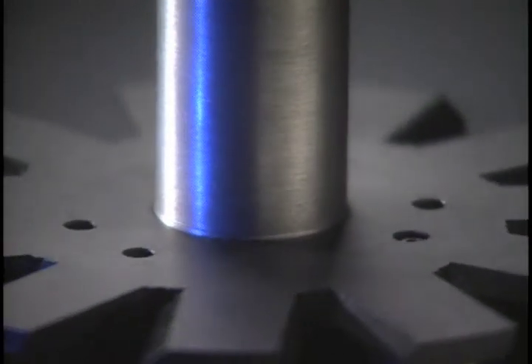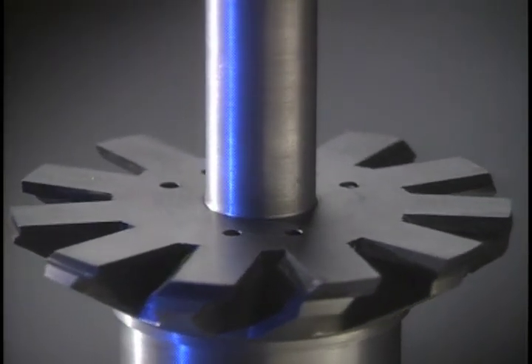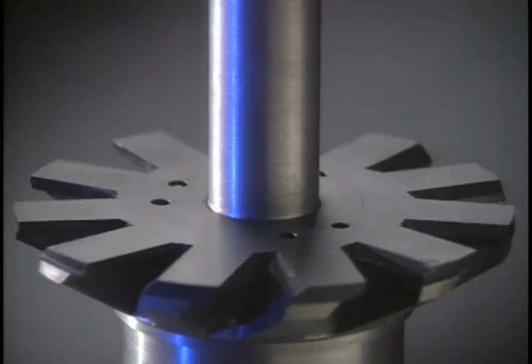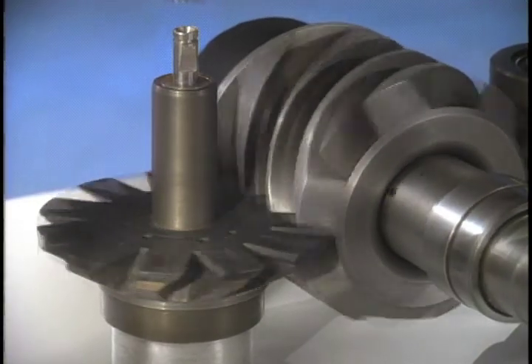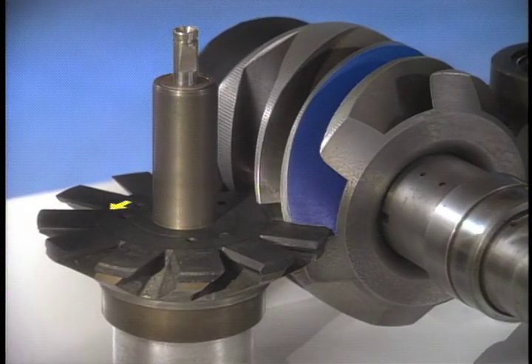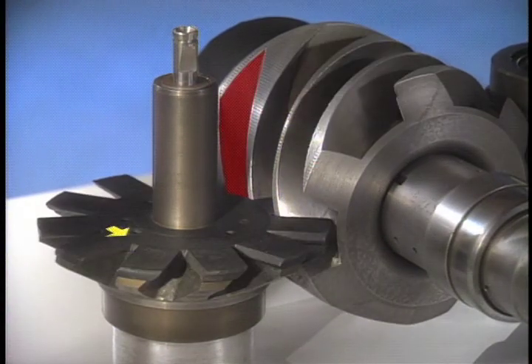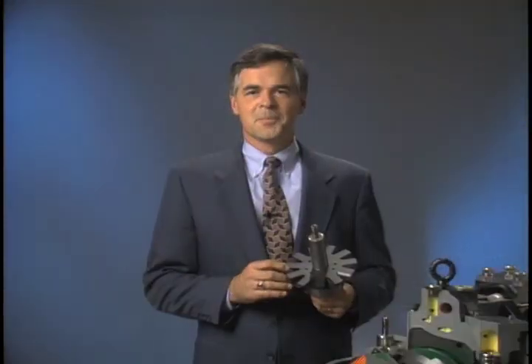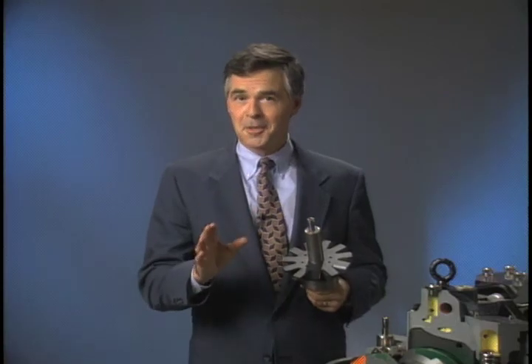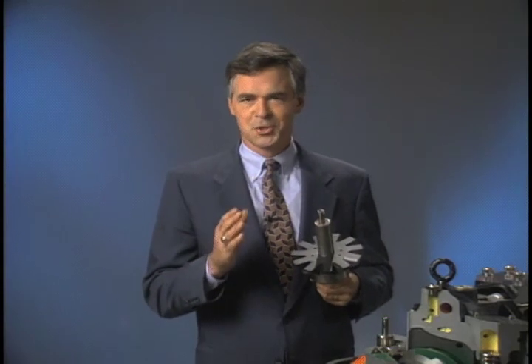Its superiority starts here with a major feat in chiller engineering. The heart of the Stargate single screw compressor is this unique gate rotor design. In operation, two of these gate rotors engage the main screw as it turns. On each side, a series of compression chambers is formed, progressively reducing volume and increasing refrigerant compression. A simple idea, but one made possible only by today's super tough materials and McQuay's remarkably precise machining.